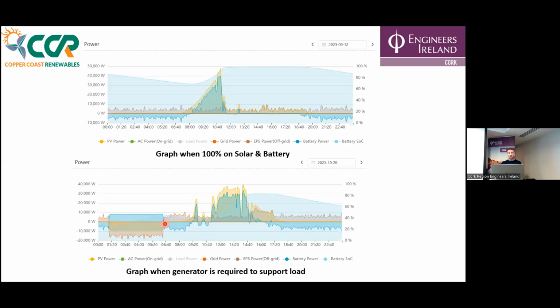Again, we don't charge the batteries up anymore because we're hoping the sun is going to come out and charge the batteries - that there'll be enough if we charge the batteries to 40%, which you can see just here on this blue line where the batteries charge up. We're hoping the batteries will last long enough until the solar comes in and tops up the batteries. And that's what you can actually see happens here on the 26th - I picked a good day for the presentation. So we charge up to the 40%.